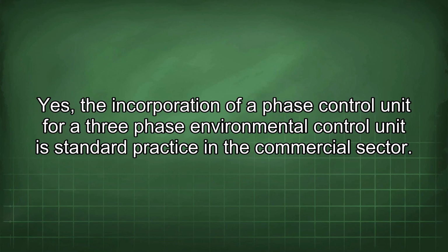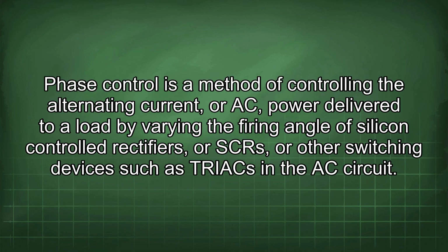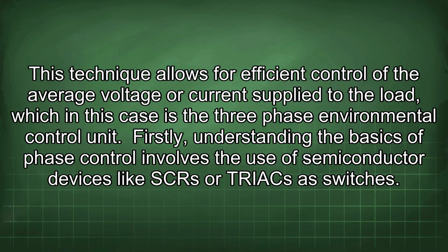Yes, the incorporation of a phase control unit for a three-phase environmental control unit is standard practice in the commercial sector. Phase control is a method of controlling the alternating current, or AC, power delivered to a load by varying the firing angle of silicon-controlled rectifiers, or SCRs, or other switching devices such as triacs in the AC circuit. This technique allows for efficient control of the average voltage or current supplied to the load, which in this case is the three-phase environmental control unit.